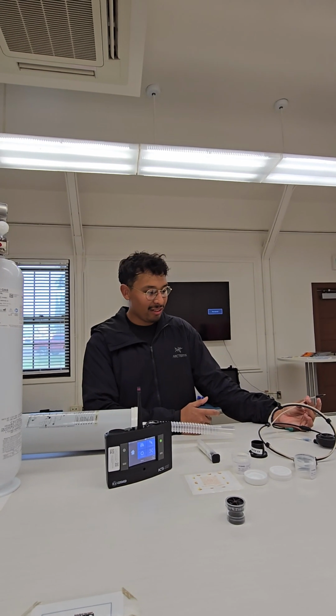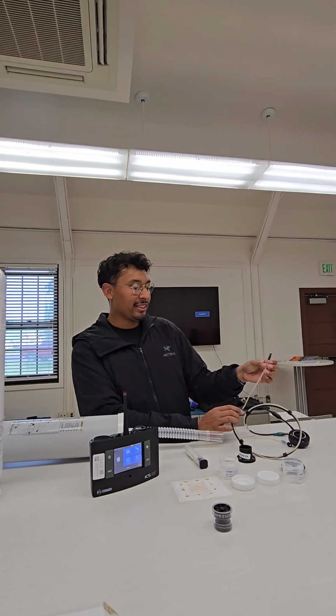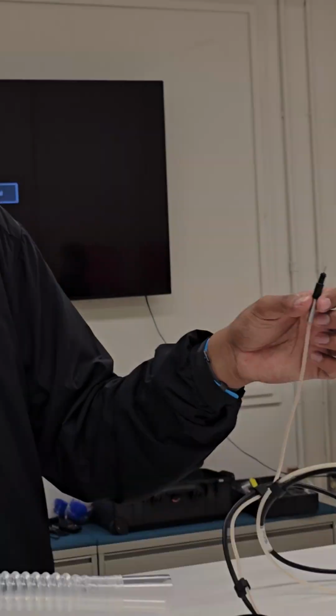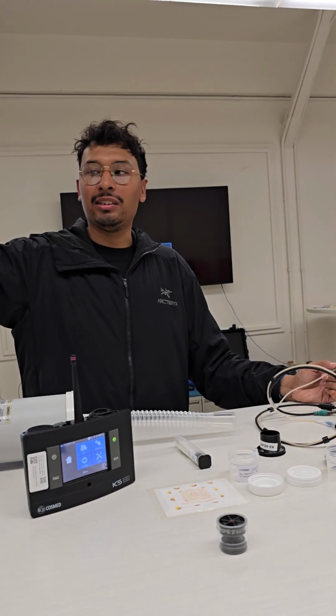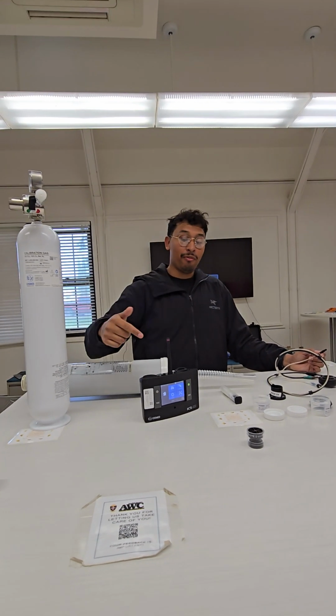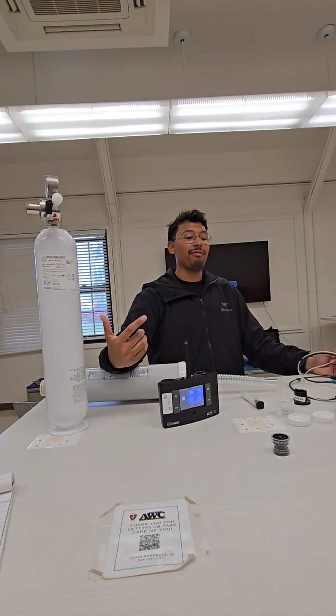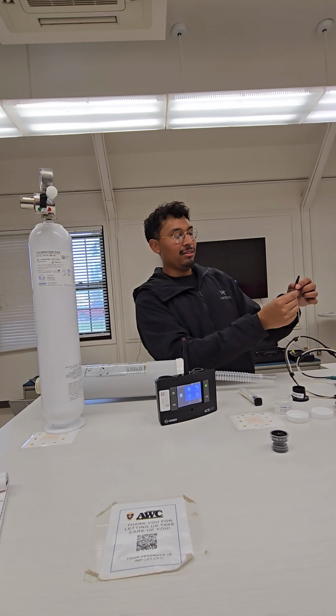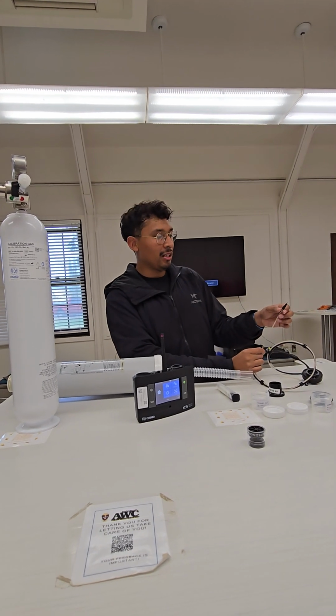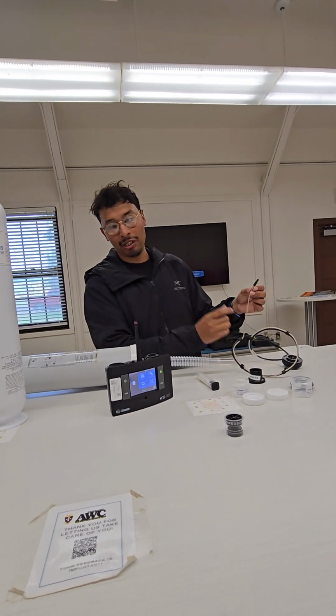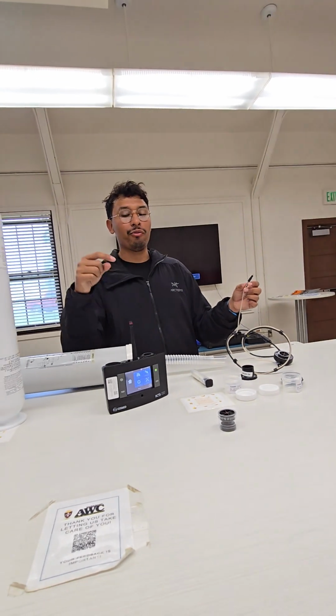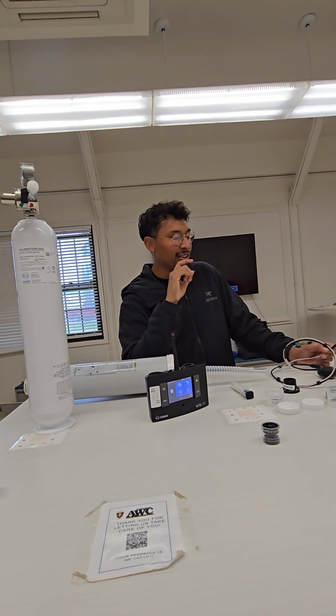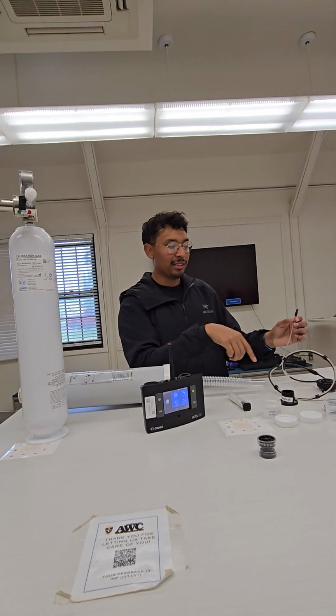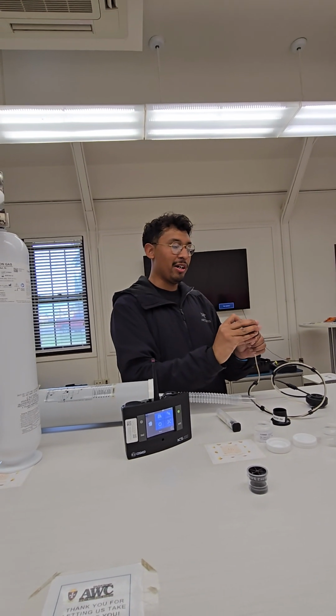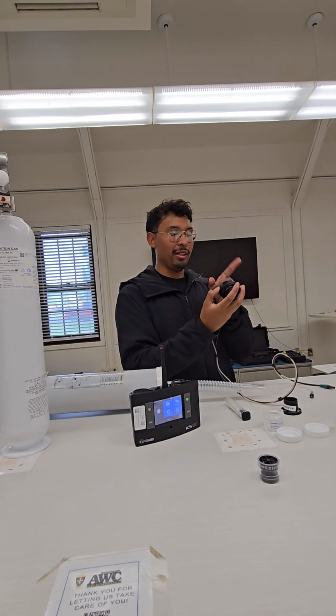And then, actually, since we're in it, the sampling lines, what they do is, basically when you're running a calibration, so when you're running this reference gas calibration, this gas is 0% humidified. Before it gets into the analyzer, it needs to have room humidity. So the material is called Nafion tubing. Basically, it just brings this air up to room humidity before it gets to the analyzers. And then when someone is breathing during a test, this guy is on the wind cap. So it'll be right here. Someone would be breathing like this.